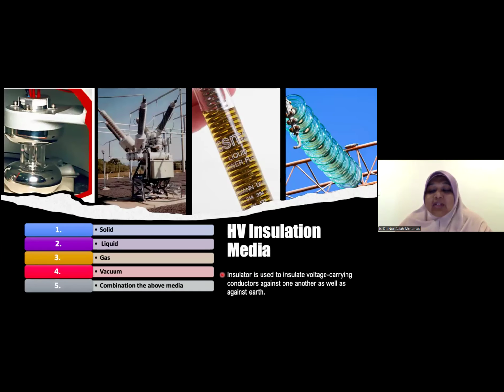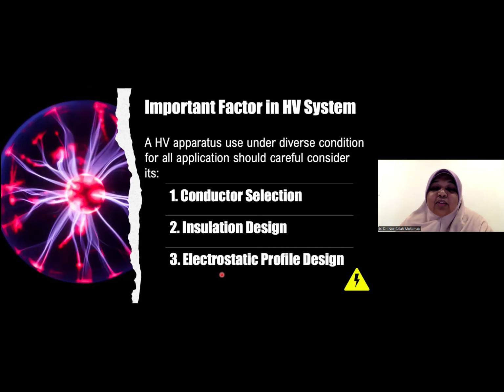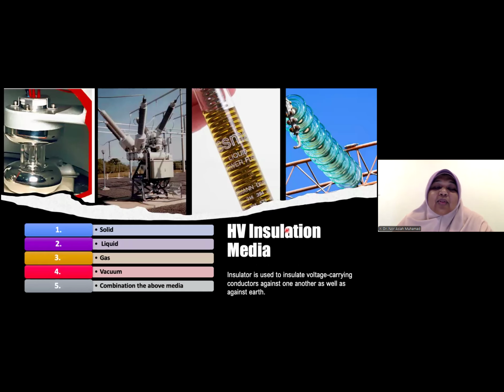But the main focus today, we are not looking at the conductor, insulation and electrostatic profiling design. The one that we are looking at is the insulation system. In high voltage insulation media, there are 5 major categories. We will go one by one: a solid insulator, then a liquid insulator, then a gas insulator. We also have a vacuum insulator, and we also have combined.